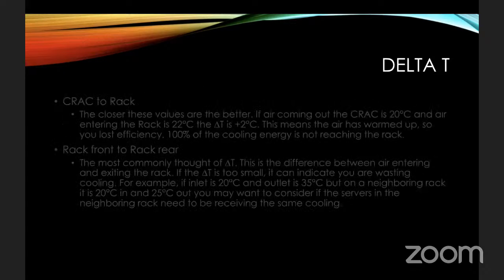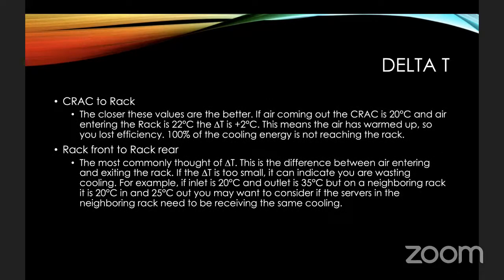So the first one of these delta Ts is the CRAC to rack. The closer these values are, the better. If the air coming out of the CRAC is 20 degrees and the air entering the rack is 22 degrees, it means you have a delta T of +2. So it means that the air has warmed up and you have lost efficiency. 100% of the cooling energy is not reaching the rack. So you are spending money on your CRAC to lower the air temperature to 20 degrees, but by the time the air reaches the rack it is 22. So somewhere that air has heated up. That means you are losing efficiency.